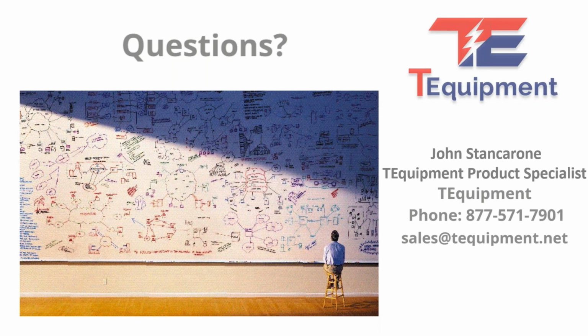Now, the best thing that you can do, especially in a solar installation where you have multiple repeated strings and the same setup multiple times, is to measure all of them and compare the values and determine what is going to be your characteristic value for that installation, if you're doing things as per the recommendations from the manufacturer. So that can establish your limits, and you can work with those.